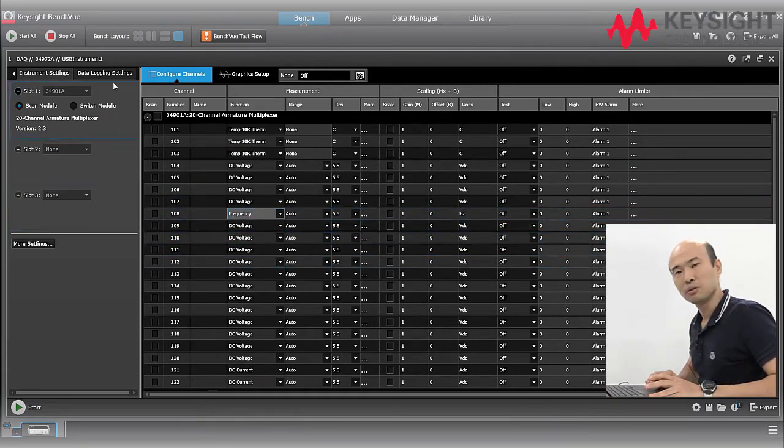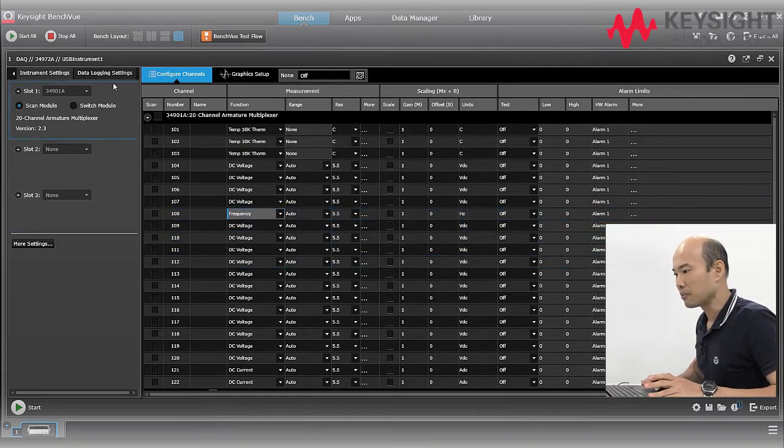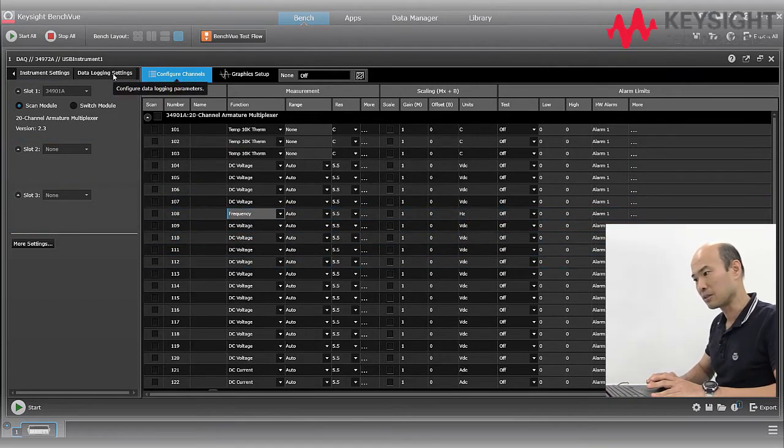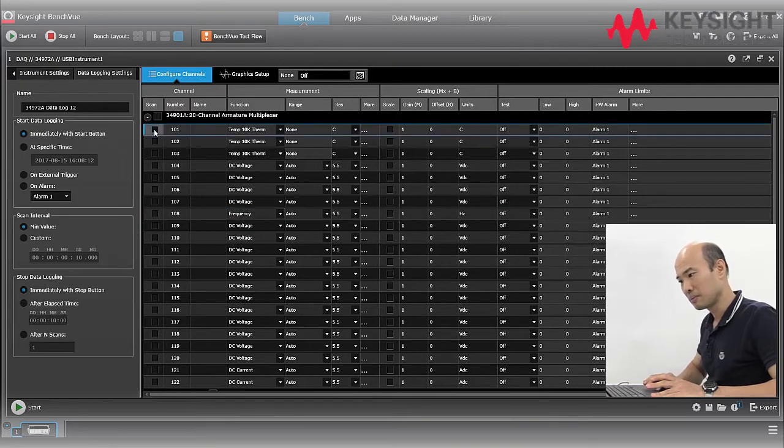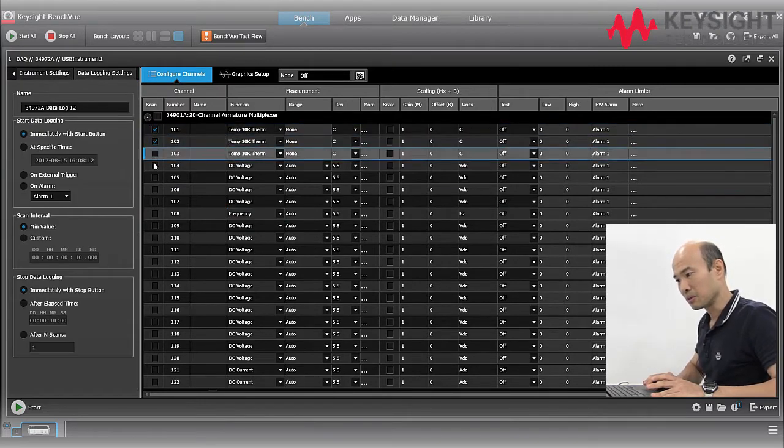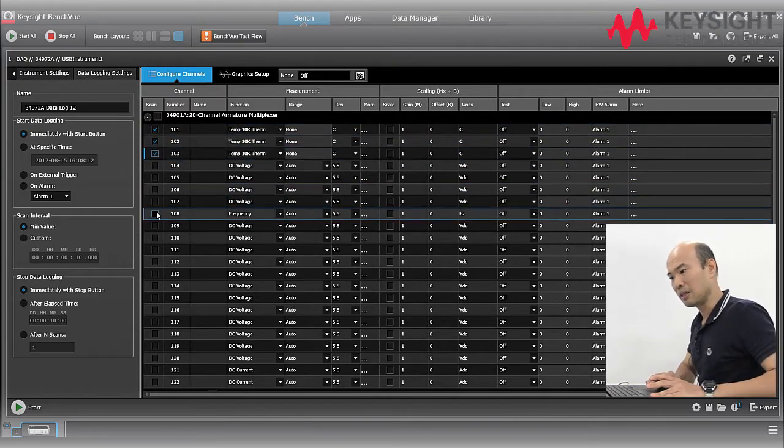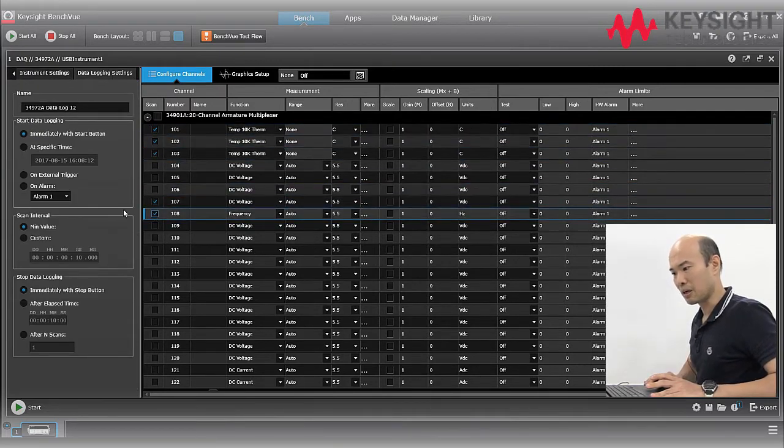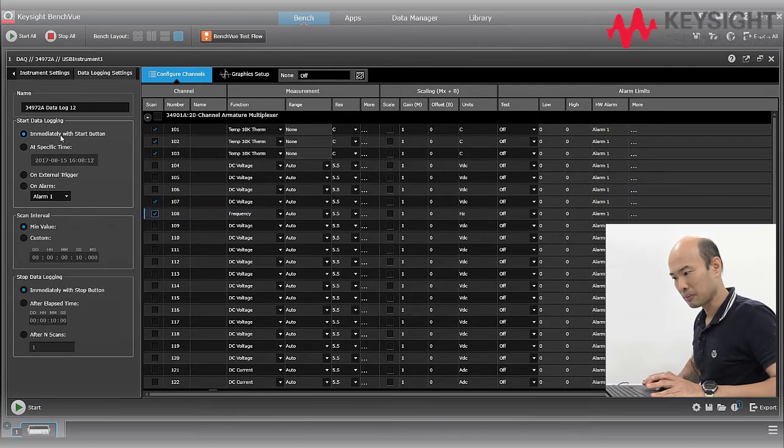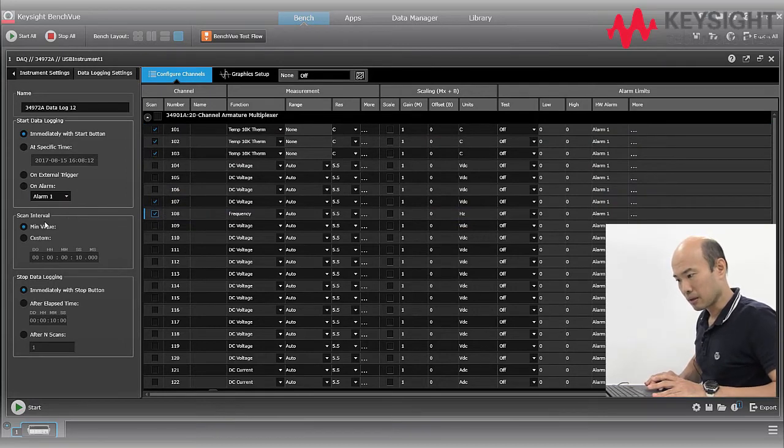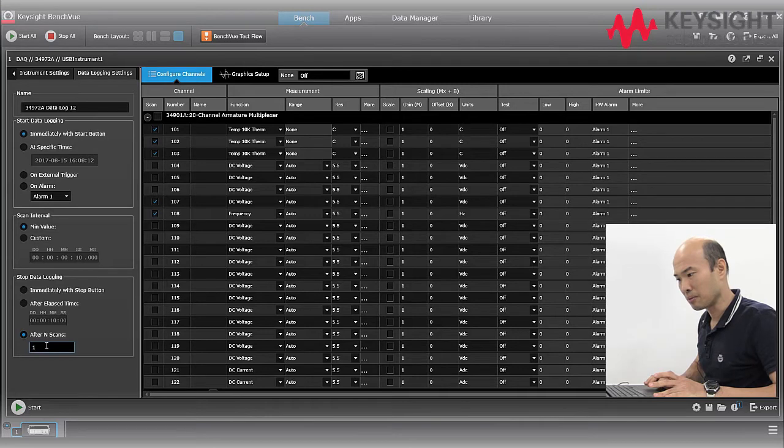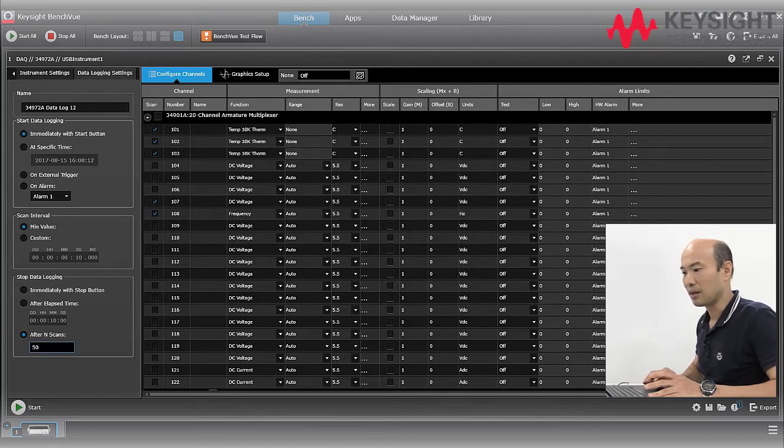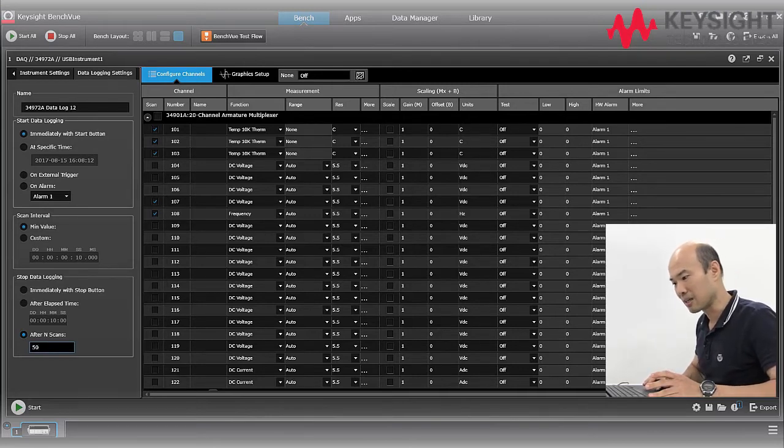So now let's set up data logging settings. We'll select immediately start with start button. We can select various scan interval but in this case we want the minimum, the fastest. And I'll stop data logging after 50 scans.